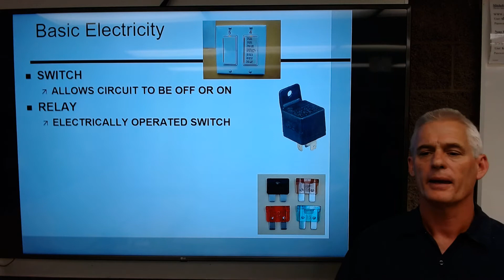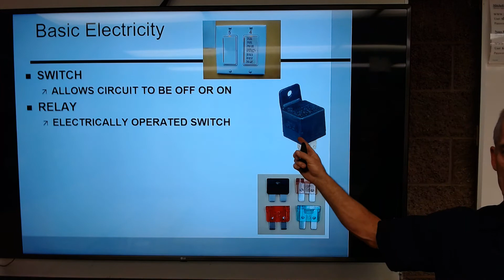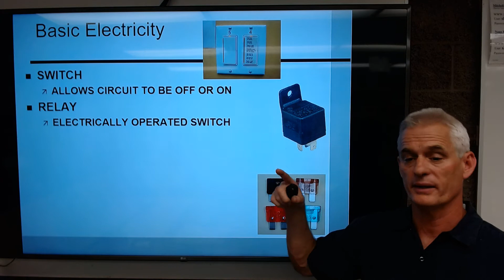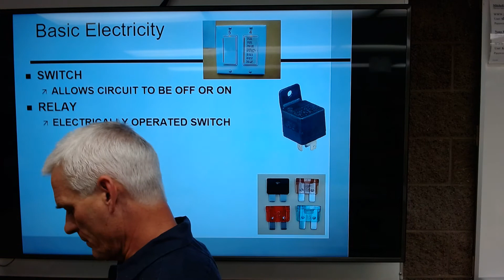So what the relay does is, when we push the momentary-on switch, the horn button, it causes a very low amount of current to flow through this relay. What limits the amount of current is the number of windings of that coil, because it has a fairly high resistance—enough coil of copper wire, and it's insulated. It's got plastic coating on it, so the little windings don't touch each other. Usually they'll have like 120 ohms of resistance.